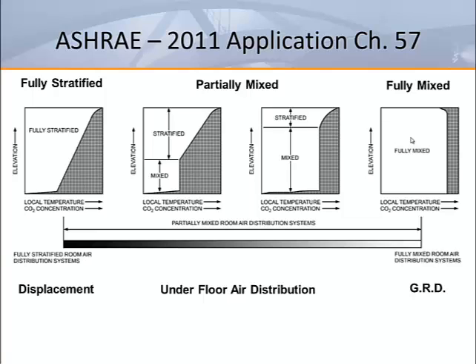A fully stratified system such as thermal displacement ventilation will discharge air horizontally from a floor-mounted or low sidewall outlet into the space. This low-velocity jet will crawl across the floor and stratify when it reaches a source of heat, such as a person or a warm piece of equipment in the space.